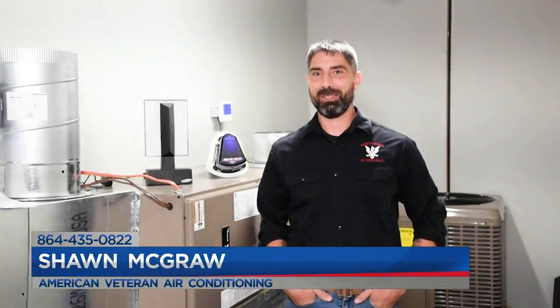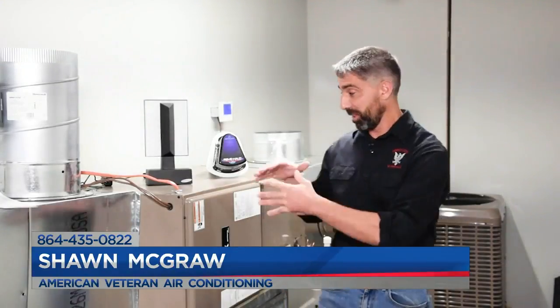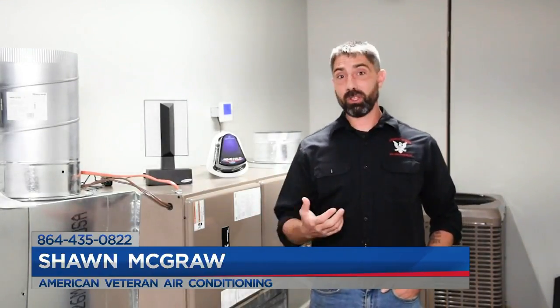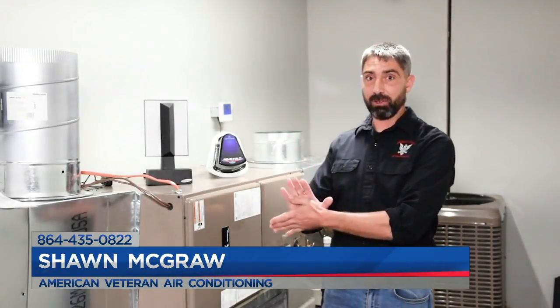Well, an air filter doesn't really make any impact on air quality, in all honesty. The purpose of an air filter is to protect your equipment, to protect this piece of equipment right here. That's what it was designed to do. When we start making them super efficient, now we're just blocking airflow. So a standard filter is what you want on the system, just to stop the major stuff from coming in and affecting your system. Anything more than that is overkill.